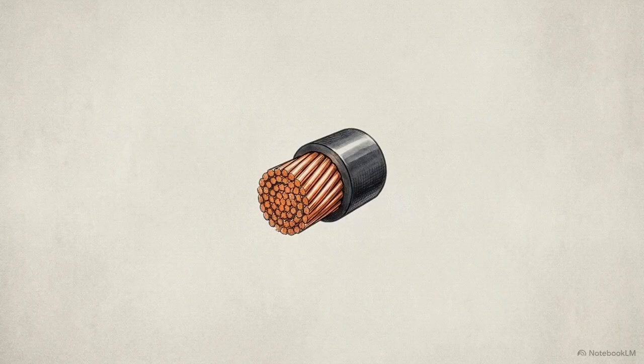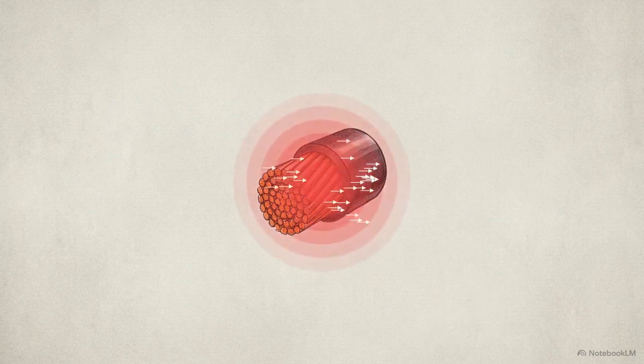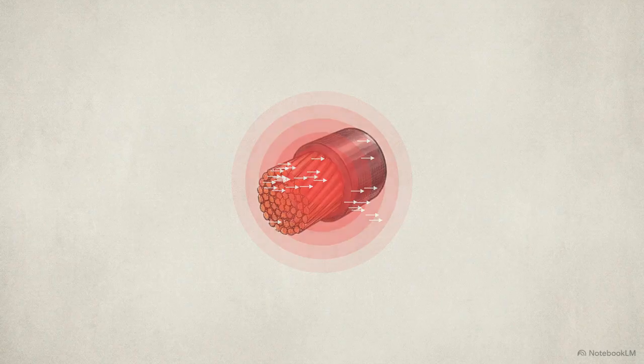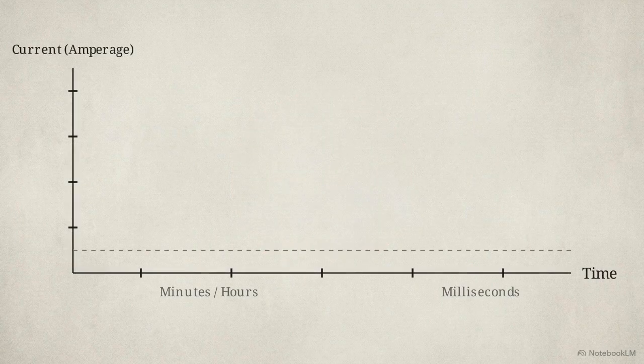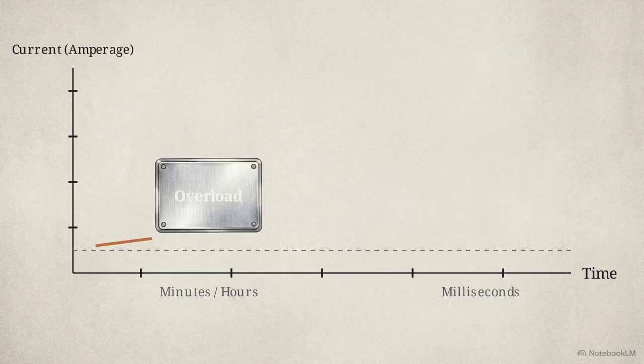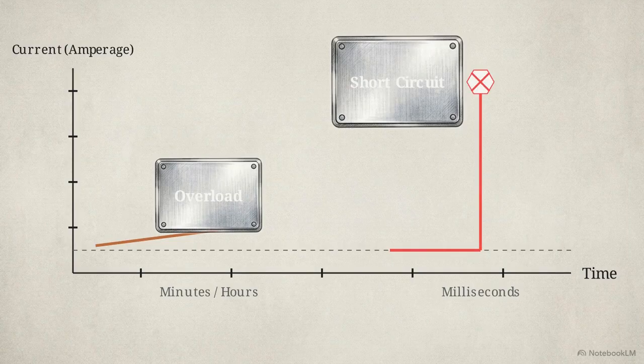An overload is a slow thermal stress caused when downstream equipment draws slightly too much current, causing wires to gradually heat up. This diagram compares the two faults. On the left, an overload takes minutes or hours to trip a breaker as thermal energy accumulates. On the right, a short circuit bypasses normal loads. Current spikes instantly into massive amperage, requiring the breaker to act in milliseconds.